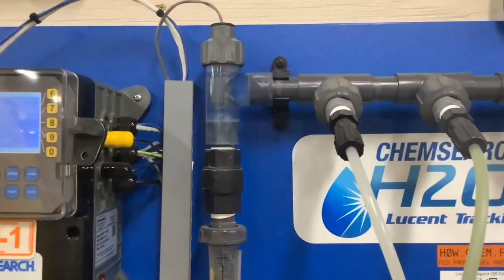Towards the top of the manifold, you will find the injection sites for your product. You can choose how many injection sites there are depending on your needs. To the left, you see the flow sensor. This sensor will relay back to the controller on whether or not there is flow at any given time through the manifold.